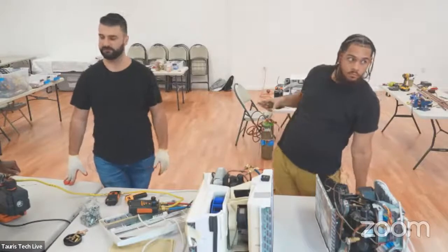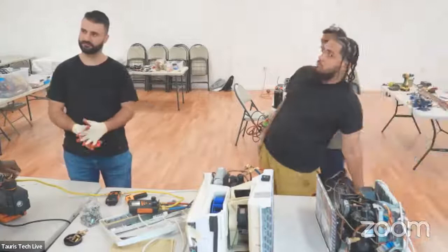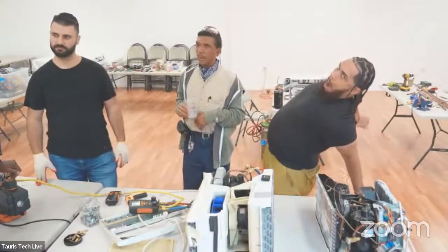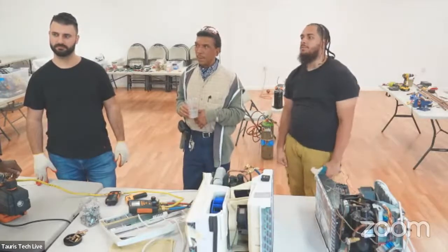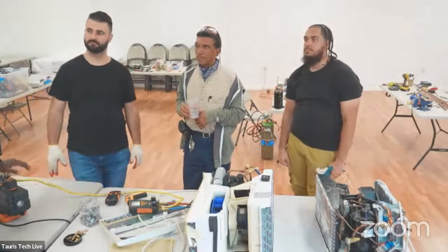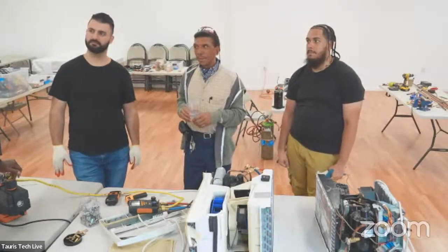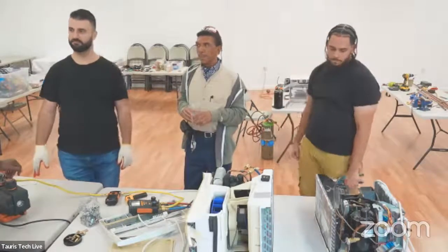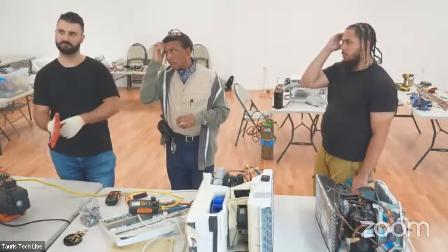And let me tell you, it's funny because the ammonia is very toxic, very toxic. So if you think about this, the ammonia you get at the store is 2% ammonia, 98% water, right? So pure ammonia, if you smell it, it'll kill you. But the problem with the lithium bromide, two problems with the lithium bromide. Number one, you got to maintain a deep, deep vacuum. So it's always sucking in air. So you always have a purger.